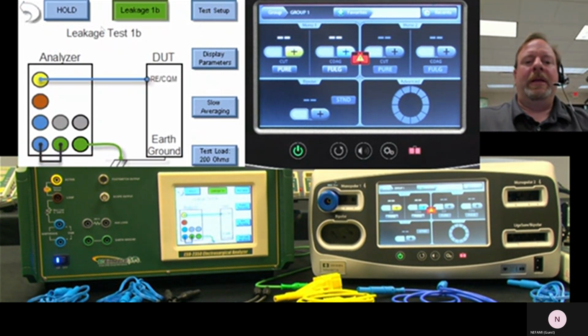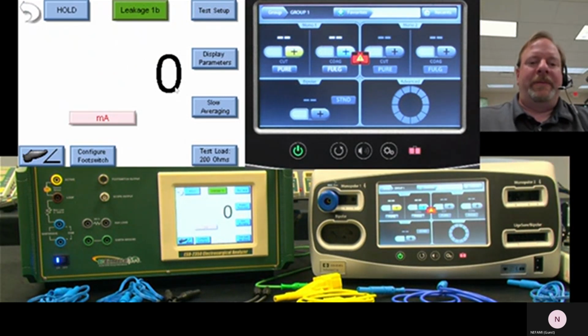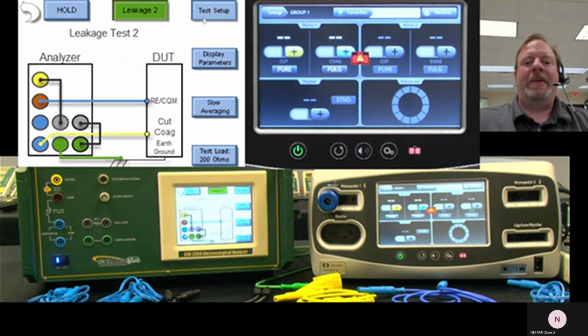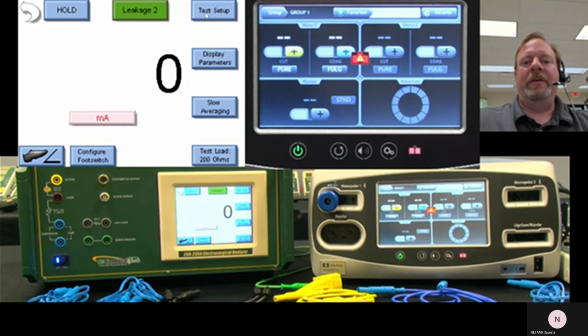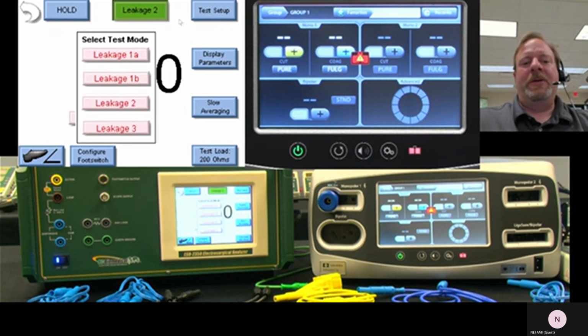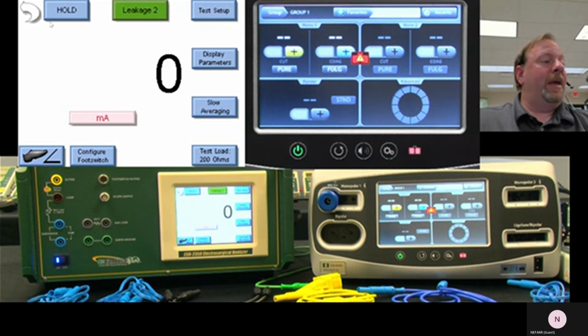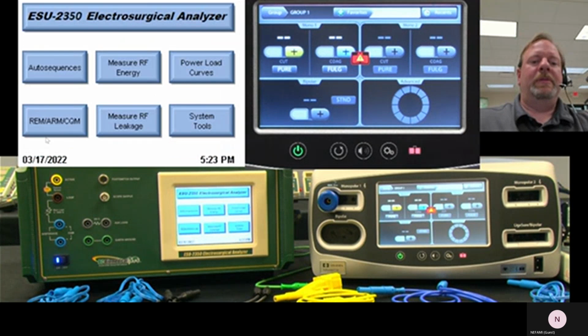So leakage mode A, leakage 1B. This is testing the return electrode. So it looks a little strange because we've got a blue cable going to the yellow terminal, but the cable's color is just a color. The main thing is that you take the return electrode of the generator to the active input, and we're measuring that current to ground. So we try to make this interface as user-friendly as possible. It tells you exactly how to configure the unit for all the testing that you need to do. And the user manual gives better descriptions than what I can do verbally here. But anyway, those are all the leakage modes. It shows you how to set them up, that sort of thing. And we'll run through the testing here, and it'll show us all of those modes that we need to.